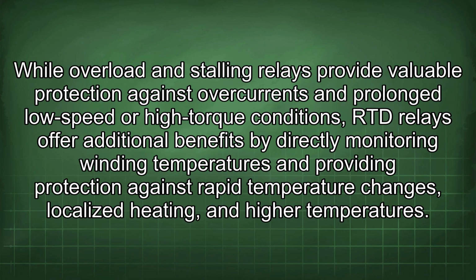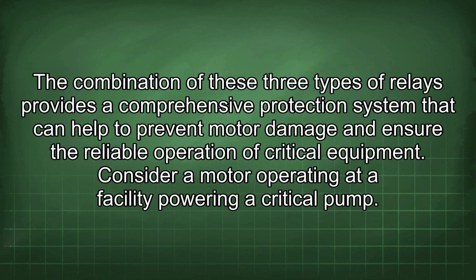While overload and stalling relays provide valuable protection against overcurrents and prolonged low speed or high torque conditions, RTD relays offer additional benefits by directly monitoring winding temperatures and providing protection against rapid temperature changes, localized heating, and higher temperatures. The combination of these three types of relays provides a comprehensive protection system that can help to prevent motor damage and ensure the reliable operation of critical equipment. Consider a motor operating at a facility powering a critical pump.